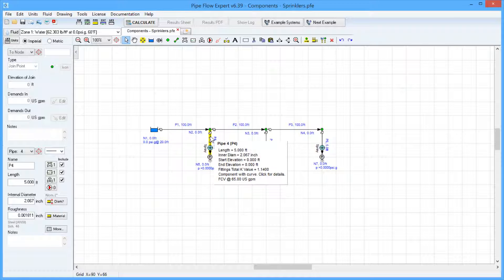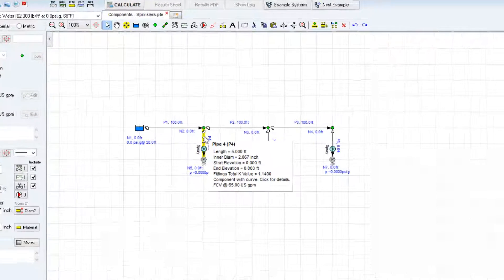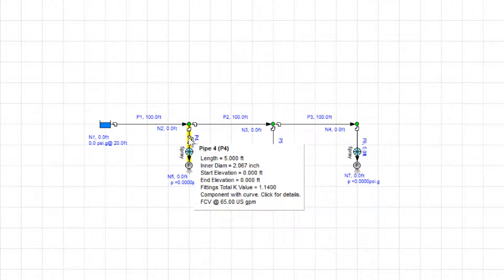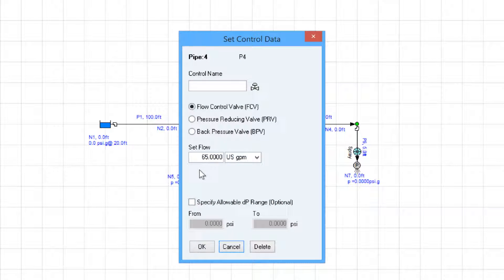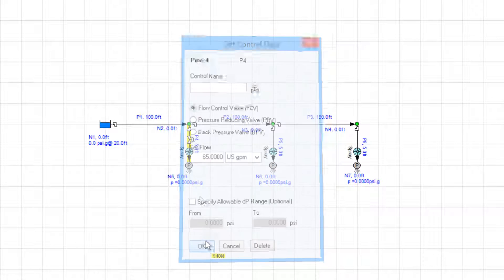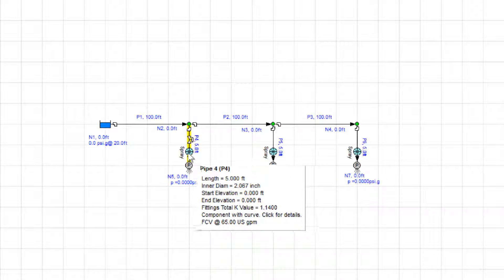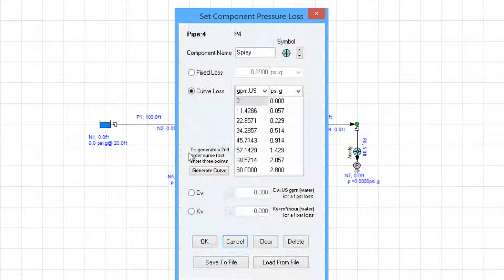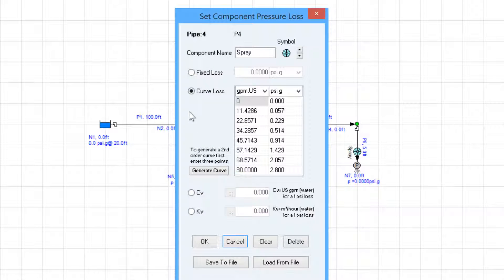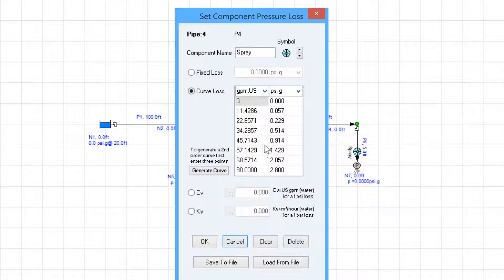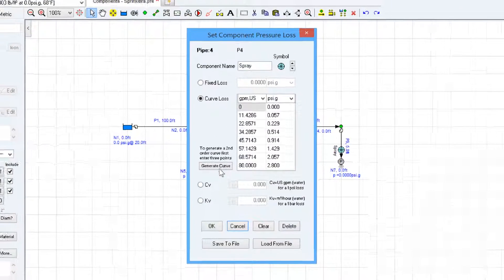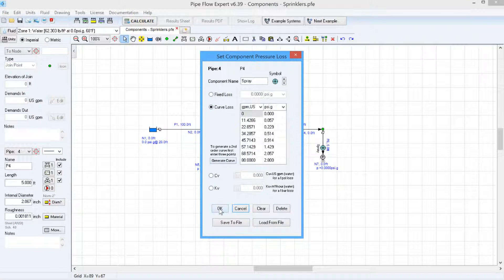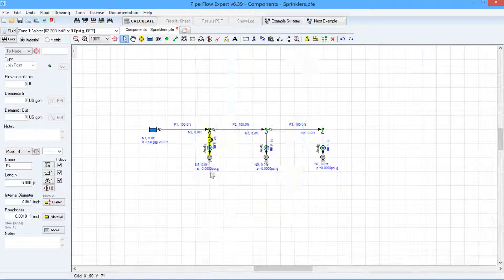On pipe 4 we have a flow control valve which has set the flow to 65 US gallons per minute and we have a component representing the sprinkler and its flow versus head characteristics have been entered into the curve loss table and we have an end pressure set to atmosphere.